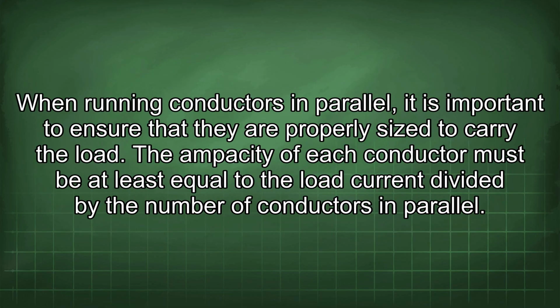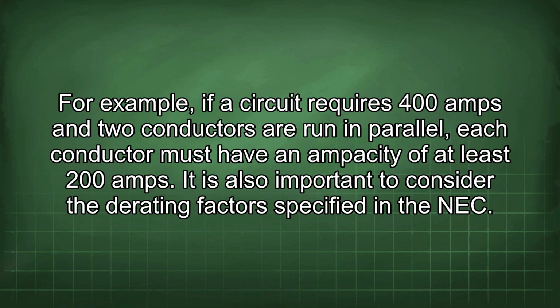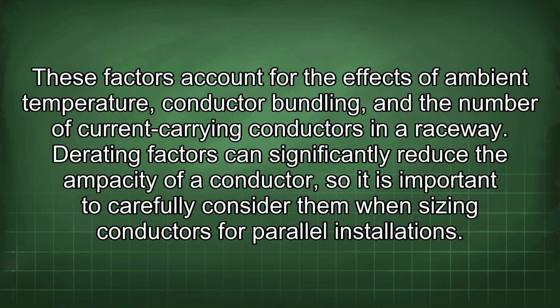When running conductors in parallel, it is important to ensure that they are properly sized to carry the load. The ampacity of each conductor must be at least equal to the load current divided by the number of conductors in parallel. For example, if a circuit requires 400 amps and two conductors are run in parallel, each conductor must have an ampacity of at least 200 amps. It is also important to consider the derating factors specified in the NEC. These factors account for the effects of ambient temperature, conductor bundling, and the number of current-carrying conductors in a raceway. Derating factors can significantly reduce the ampacity of a conductor, so it is important to carefully consider them when sizing conductors for parallel installations.